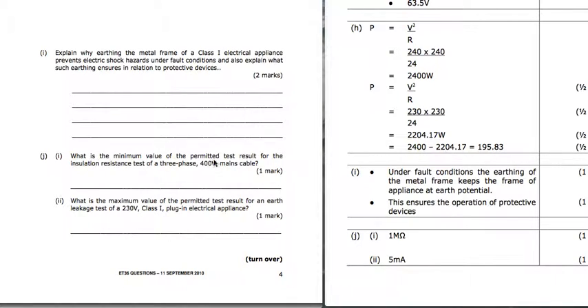Minimum value of permitted test result for insulation resistance. So insulation resistance, 1 mega ohm, should trigger that straight away. 400 volt mains cable, so don't be fooled by the voltage, it's still 1 mega ohm. Here we are there. The maximum value of permitted test result for an earth leakage. So the earth leakage test, we can allow up to 5 milliamps to flow. So that's our maximum value, 5 milliamps.